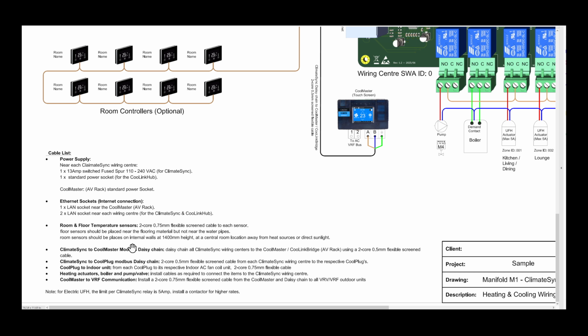Room sensors, the best is to place them on internal walls, not on external, as they will be influenced by external wall temperature. So on internal walls, the recommended height is 1.4 meters from the floor, in a central room location, away from any heat source or direct sunlight.